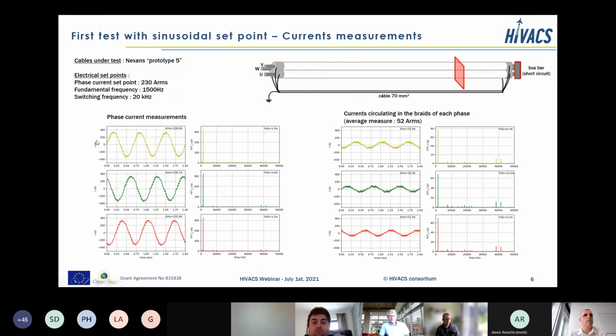For example, we impose 230 ampere in the conductor, but we got 50 ampere in the shield, and these induced currents are quite well balanced. It's like a new three-phase induced system, because if we sum all the three currents, we are quite equal to zero. So well balanced currents in this system.